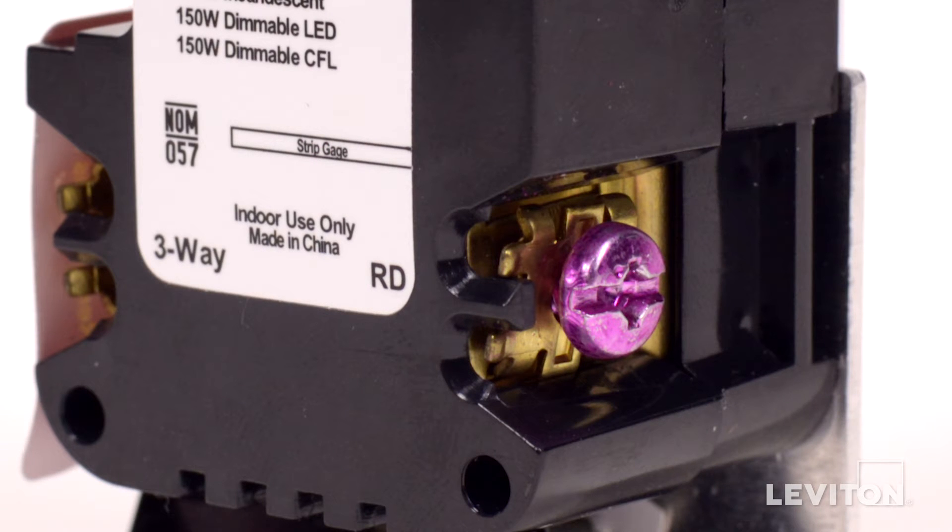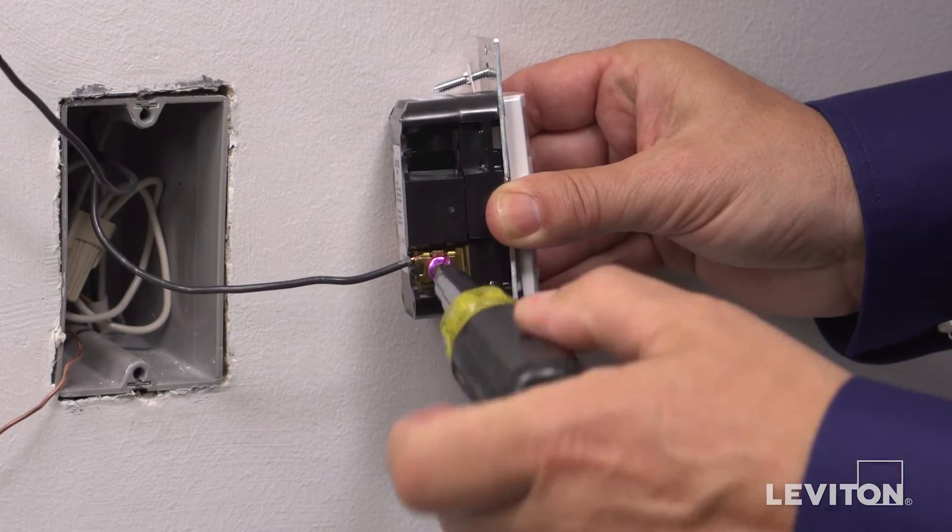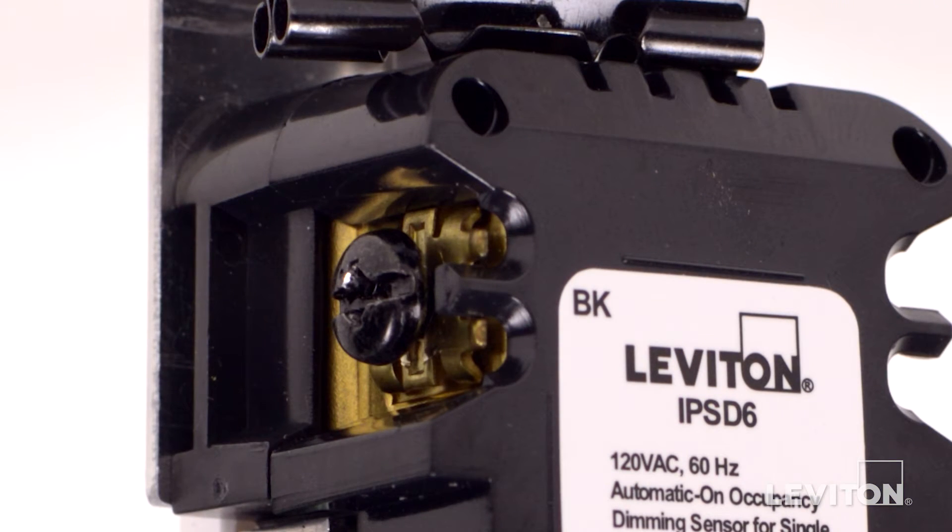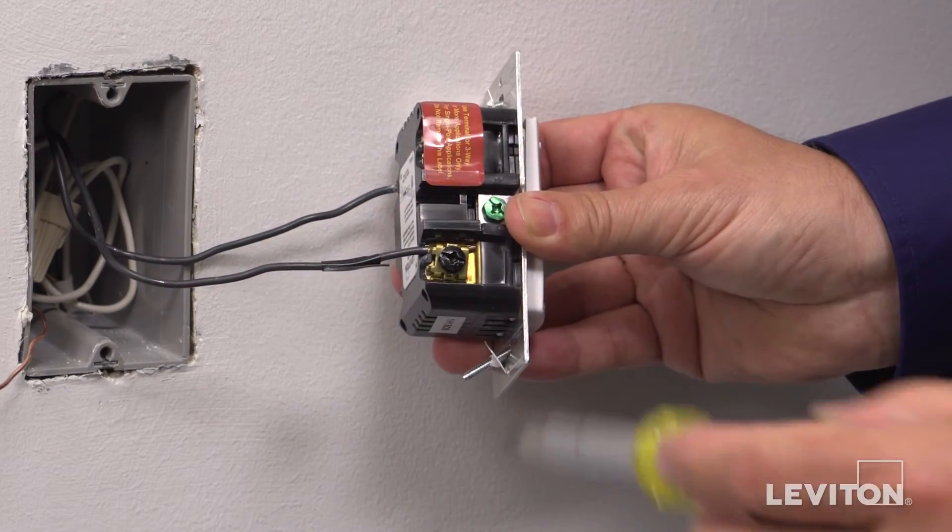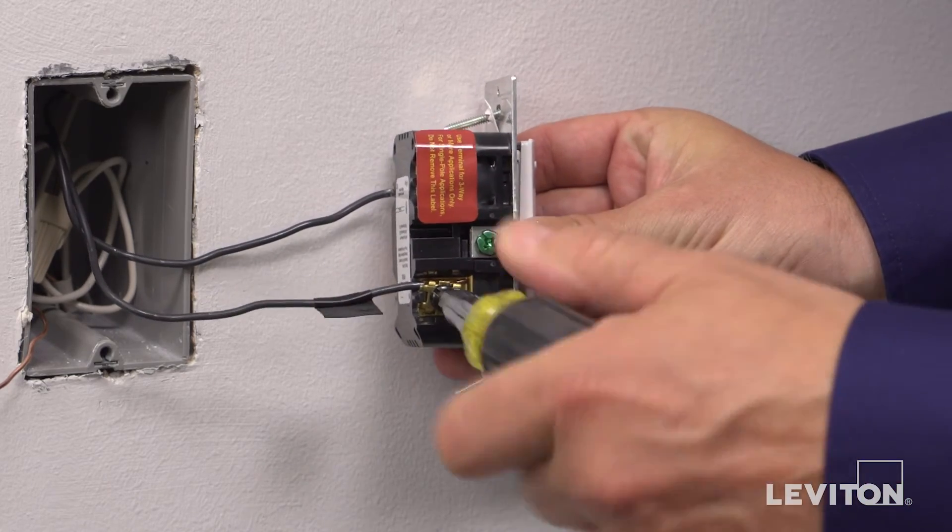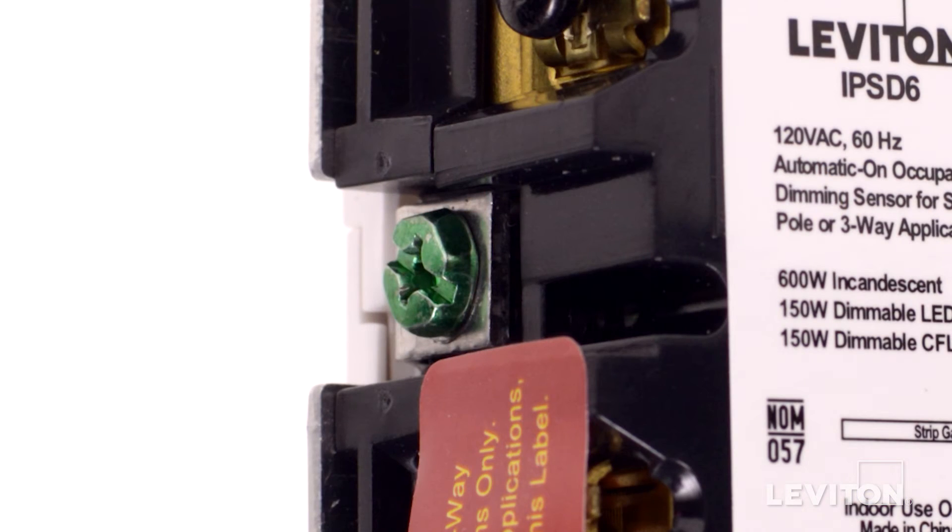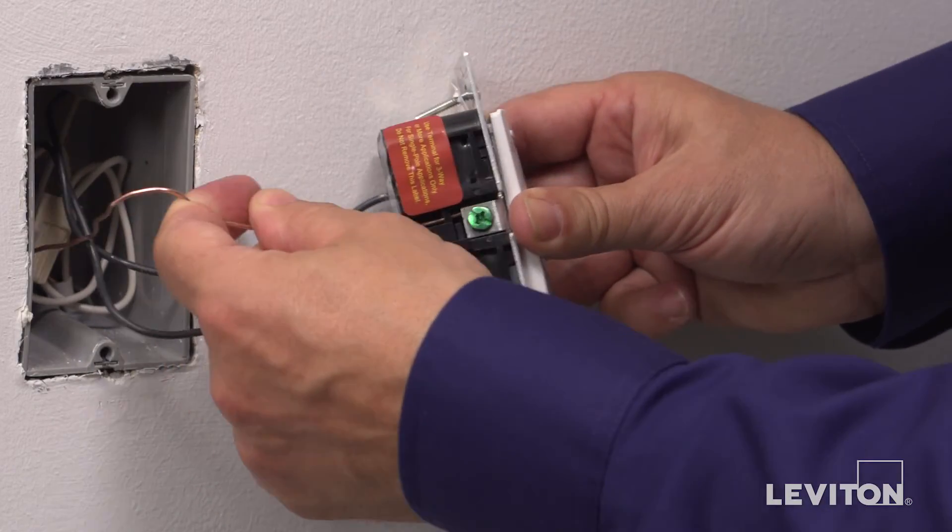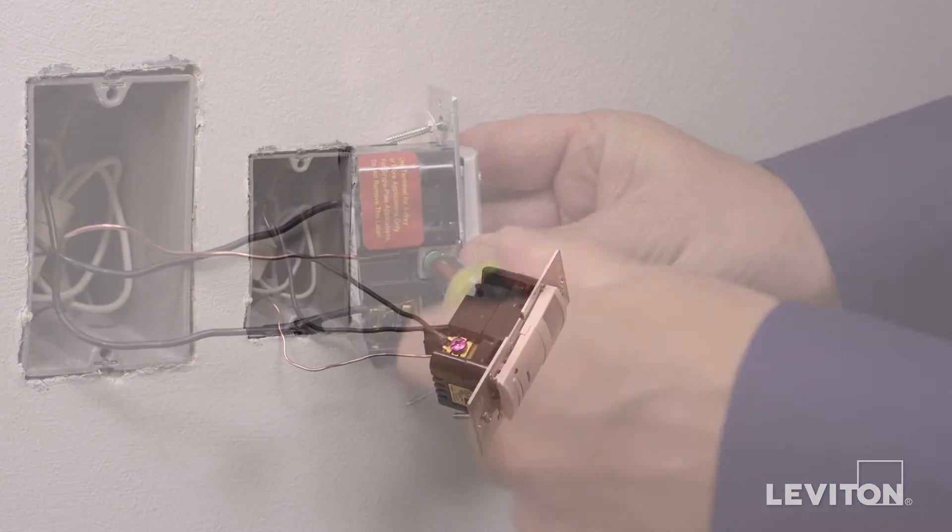Connect the load wall box wire to terminal screw marked RD. Connect the line hot wall box wire to the terminal screw marked BK. Connect the green or bare copper wire in the wall box to the green terminal screw. The device is now terminated.